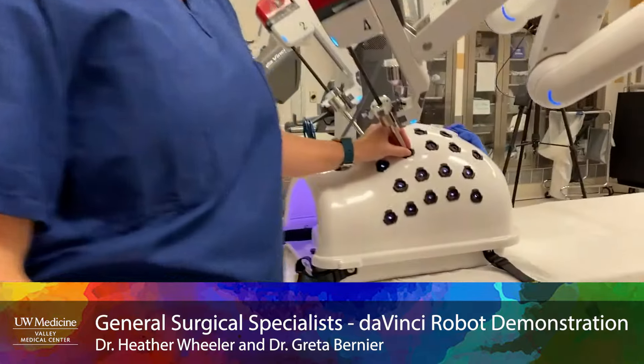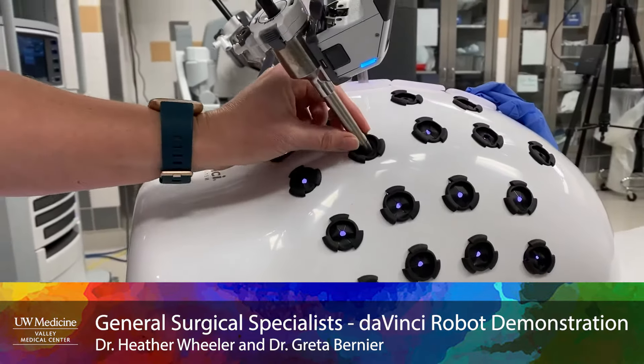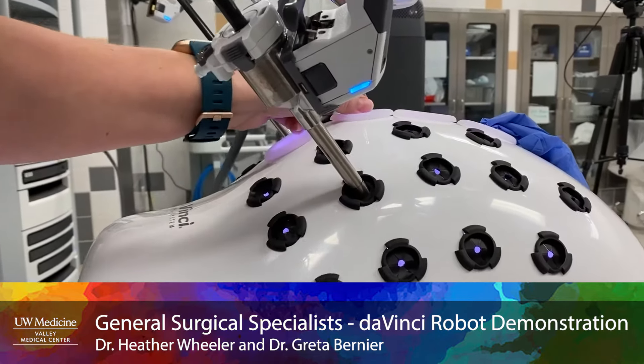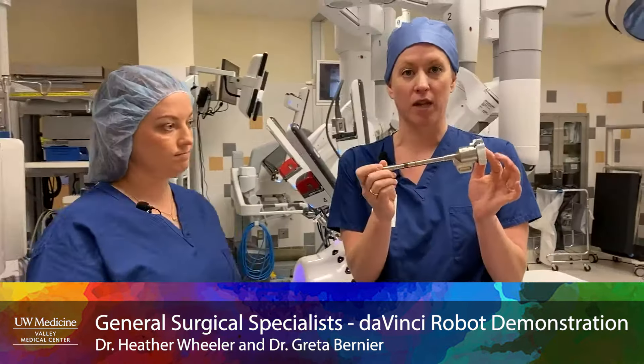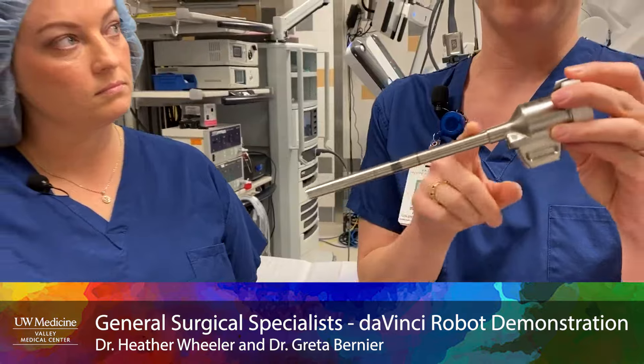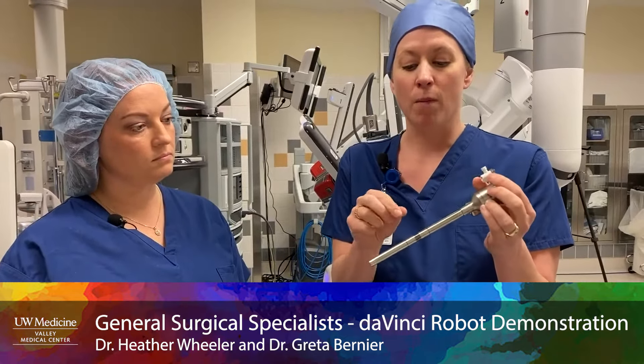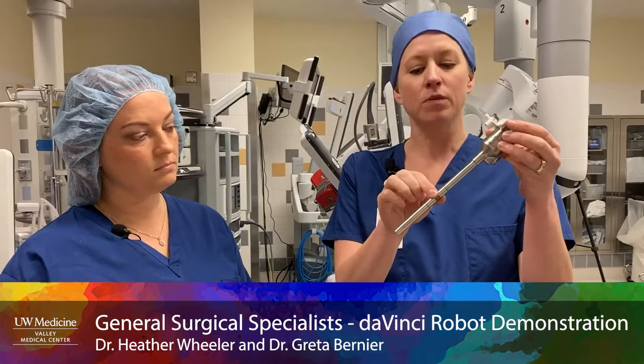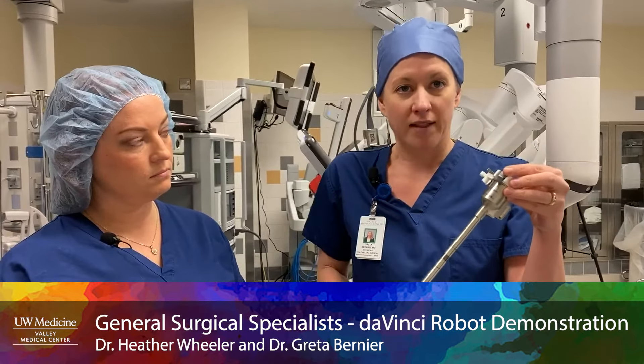We already have this docked here to demonstrate what it looks like for a patient. These are the trocars or the ports — those mean the same thing — but they would be going into small keyhole incisions in a standard patient. We attach the patient cart to these trocars and insert the instruments through them. One of the things that's really cool about the robot is this fat black band right here, called the remote center. If you imagine moving an instrument around, we could torque and put a lot of tension or pressure on the abdominal wall — but the robot knows exactly where the remote center is, so anytime we're moving an instrument it rotates around that point. It's not torquing on the belly wall the same way a laparoscopic instrument would, which we think is a big part of why there's less pain.